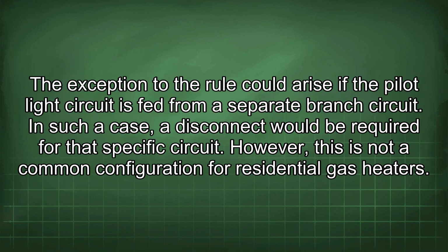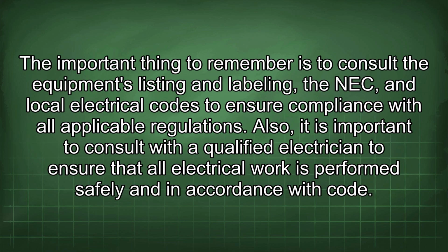The exception to the rule could arise if the pilot light circuit is fed from a separate branch circuit. In such a case, a disconnect would be required for that specific circuit. However, this is not a common configuration for residential gas heaters. The important thing to remember is to consult the equipment's listing and labeling, the NEC, and local electrical codes to ensure compliance with all applicable regulations.